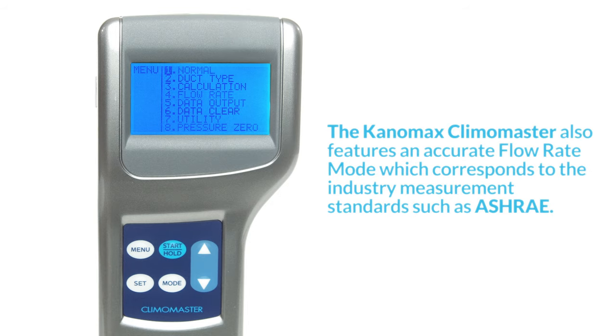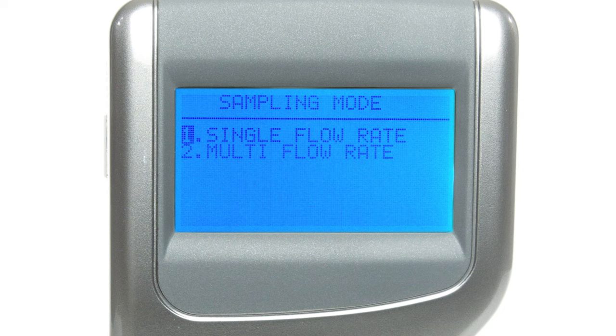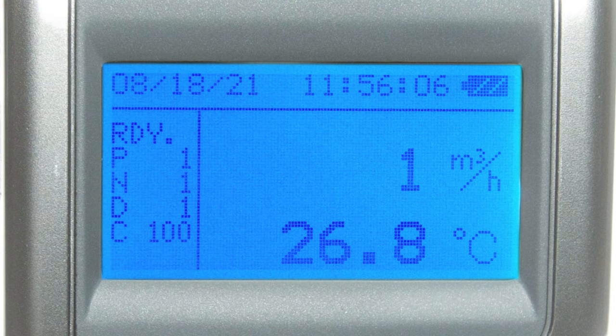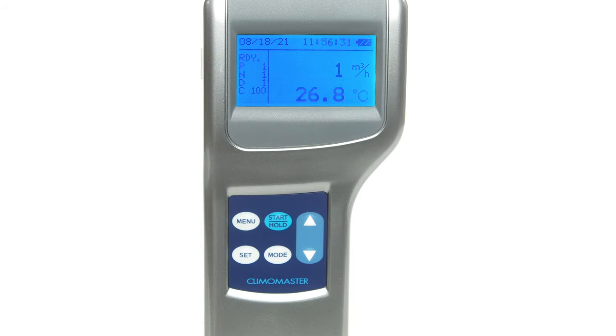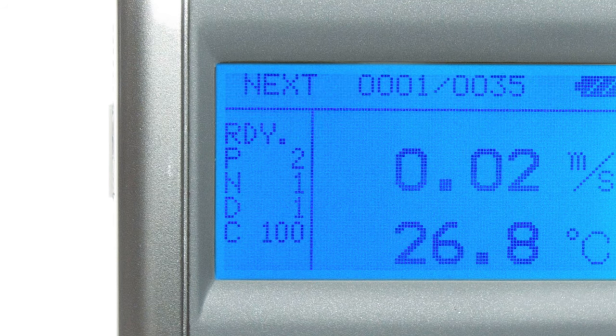The Kanomax Climomaster also features an accurate flow rate mode which corresponds to industry measurement standards such as ASHRAE. This mode is useful for performing a measurement of the airflow of ductwork. From the main menu, select flow rate. Under this section you have the option of choosing single or multi flow rate — select single. Configure your setup similar to how you would in calculation mode, this time configuring how many measuring points you want to include and which number duct entry is being measured. Select set to start to be brought to the ready screen. On screen, P stands for current number of points, N for current number of samples, D for the selected duct entry number, and C or R for the duct shape and size. To stop the measurement press start or hold; to continue press it again; and to complete the measurement press set. Then the results will be displayed.